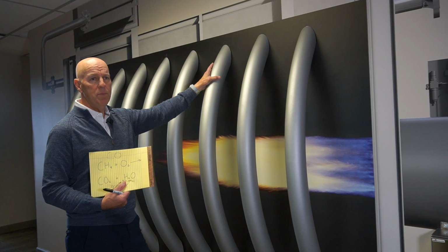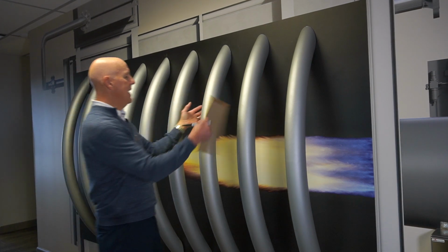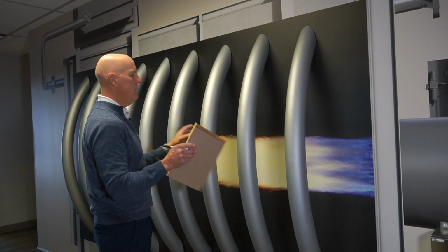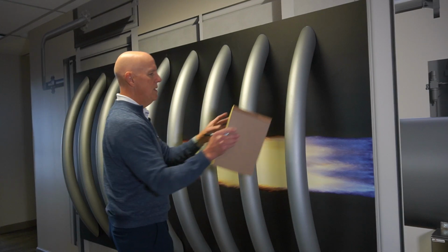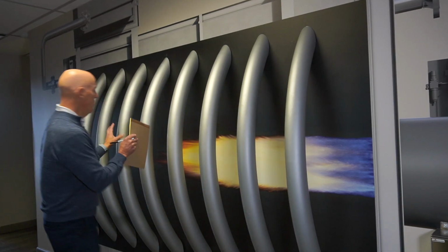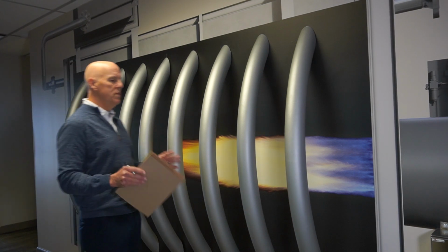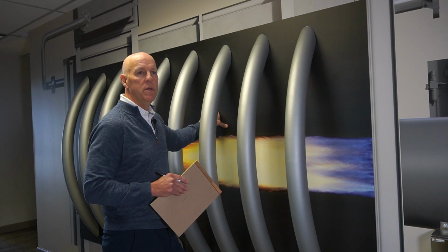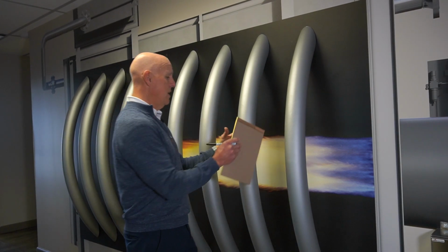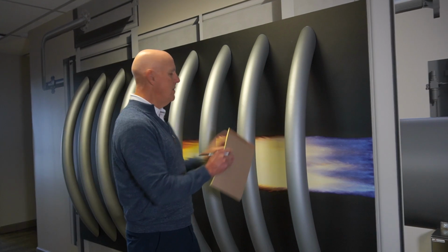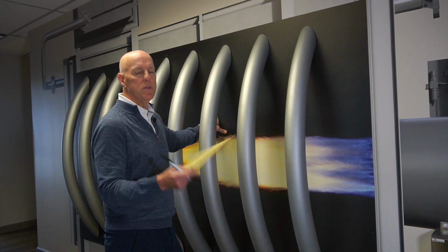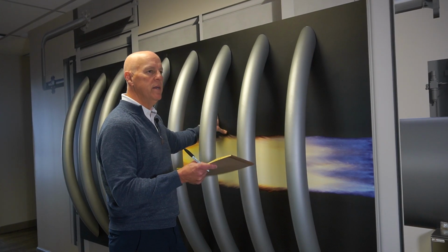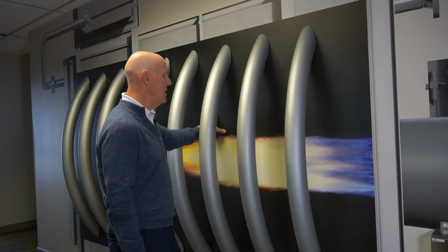I can take ceramic fiber blanket, which is flexible, and I can wrap this tube. Maybe I don't wrap all of them. Maybe I wrap two thirds of them. So maybe wrap these two, leave this one bare, wrap these two, leave this one bare. And with that, what happens? Well, obviously this cold environment starts to warm up. As I eliminate places for the heat to go, this environment heats up, and guess what? The CO burns out. So that allows me to have a heater that's maybe too big to still achieve the emissions requirements that it needs to achieve.